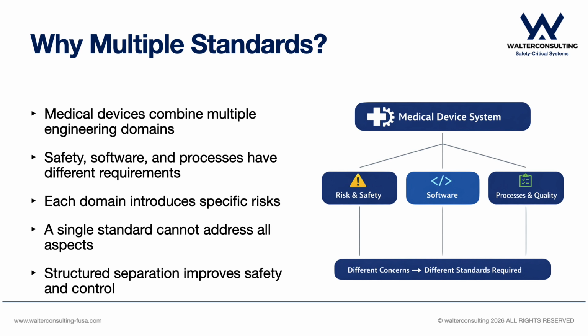Why do we actually need multiple standards? Let's think about what a medical device really is. It is not just hardware. It includes software. It interacts with users, and it operates in a safety-critical environment. So here is the question. Can one single standard really cover all of this? Risk management, software behavior, and development processes all have very different requirements. Each of these areas introduces its own challenges, and more importantly, its own risks. This is why medical device development is split into different domains, and each domain is addressed by a specific standard.